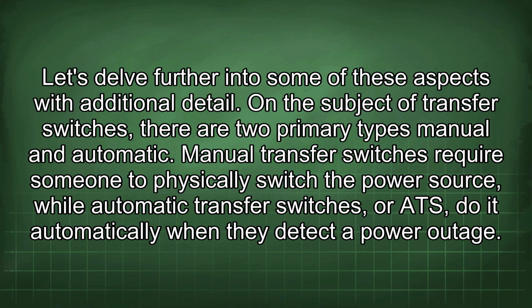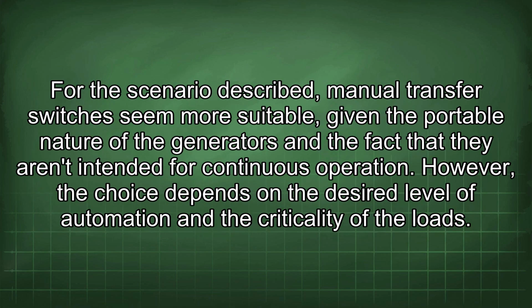On the subject of transfer switches, there are two primary types: manual and automatic. Manual transfer switches require someone to physically switch the power source, while automatic transfer switches, or ATS, do it automatically when they detect a power outage. For the scenario described, manual transfer switches seem more suitable, given the portable nature of the generators and the fact that they aren't intended for continuous operation.